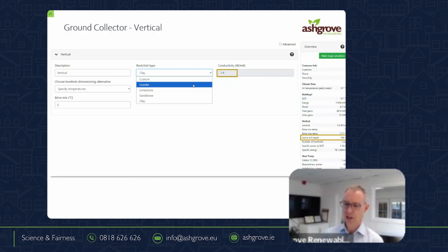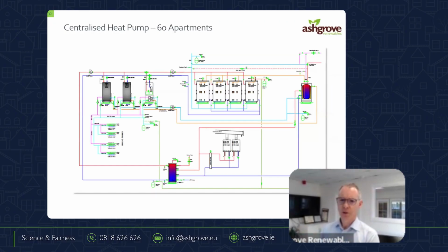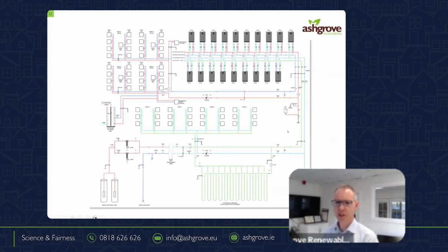But if I undersize that and over the year, I'm taking out more energy out of the area surrounding the pipe than it can naturally replenish because of conductivity, well, the brine temperature drops and my COP starts to drop away fairly dramatically. So I won't spend much more time at that. I'm actually going to skip that one, Johnny, given the time.